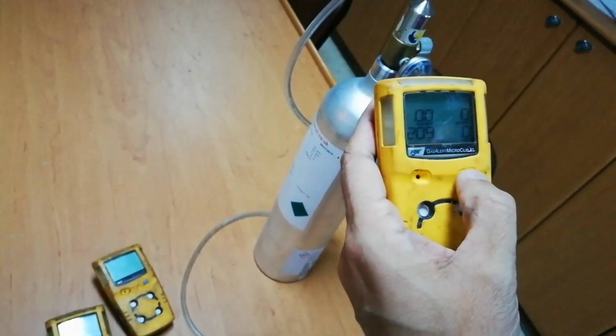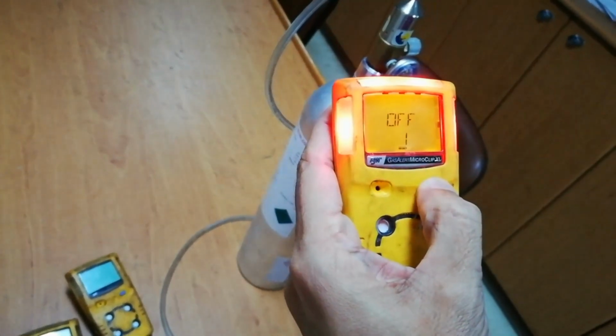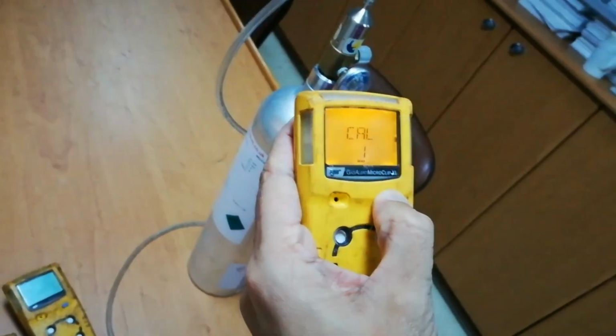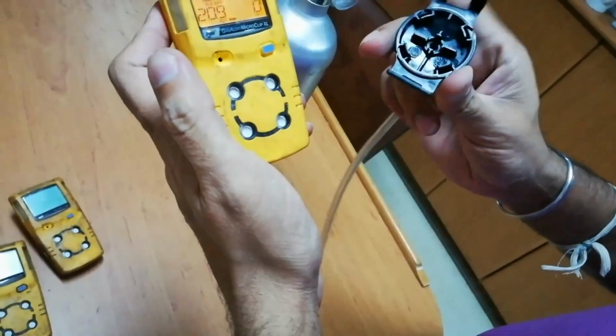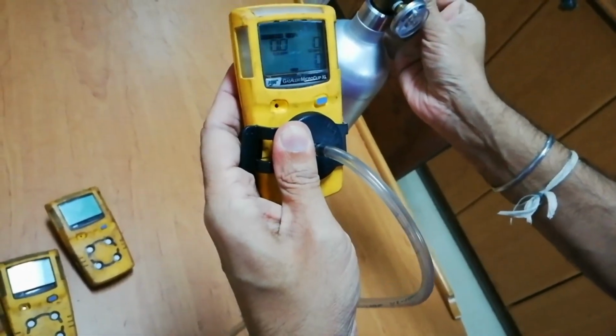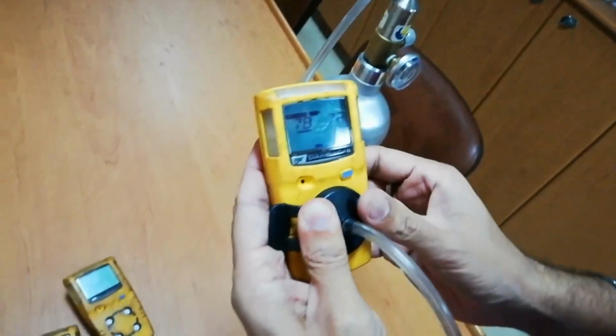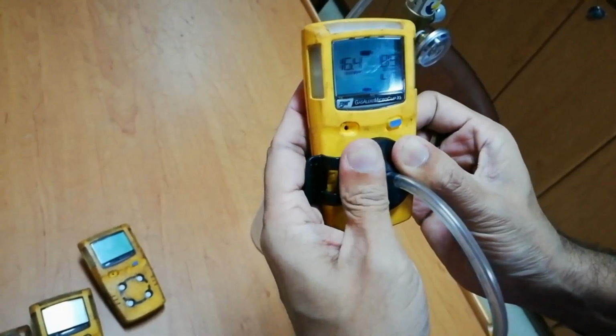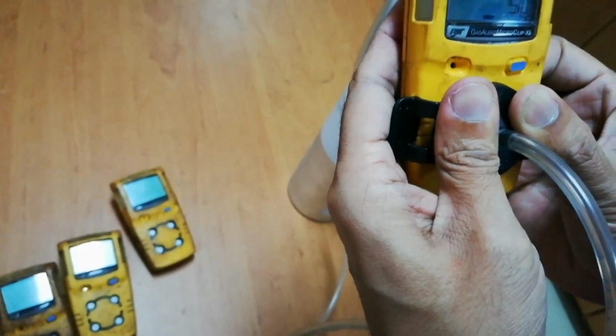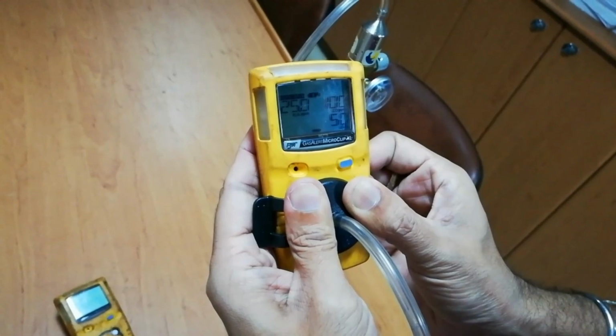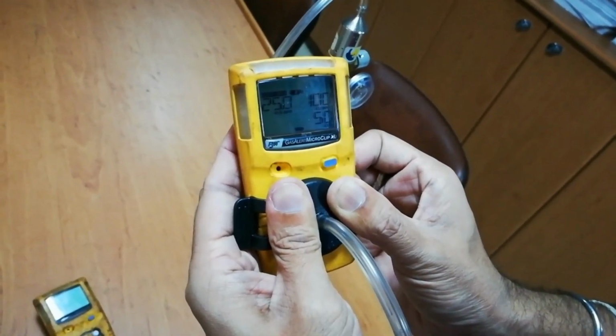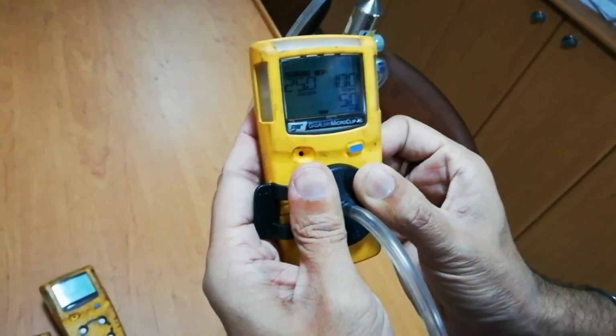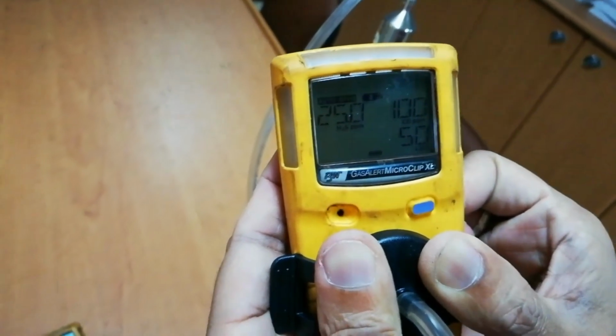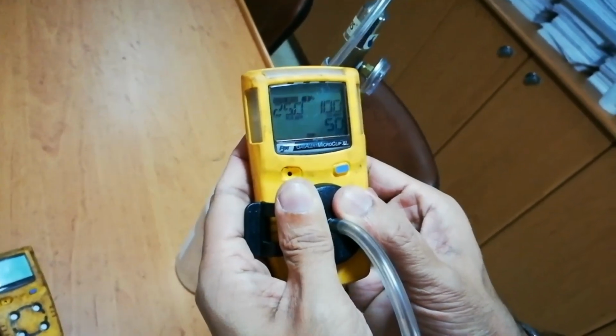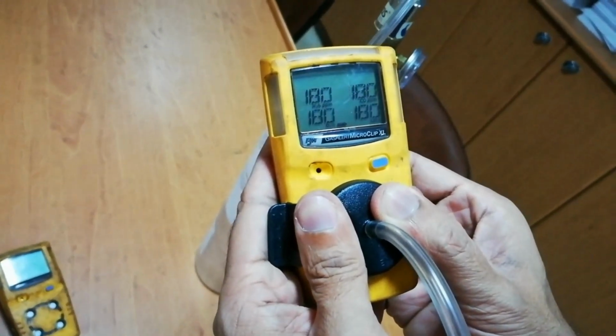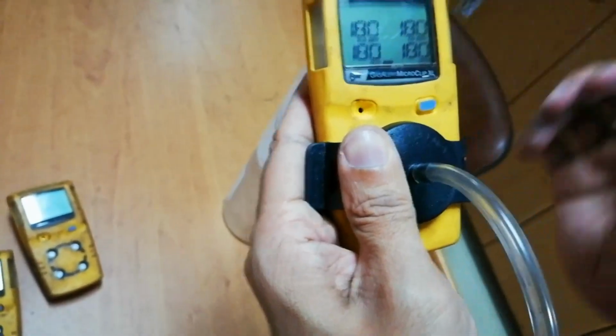First I will switch off the multi-gas detector, and I will keep pressing this power off button. Now we are in calibration mode, and it will ask to supply span gas. So we will connect this calibration hose and apply the span gas, and keep holding this calibration adapter. The figures should be the same as the span gas content. Here you can see on the left side H2S 25 ppm, on the right side 100 ppm for carbon monoxide, and down below 50% of the LEL. H2S, carbon monoxide, and LEL are the same as the span gas, and we will wait a little. Now the calibration is done, and it is showing calibration due in 180 days.